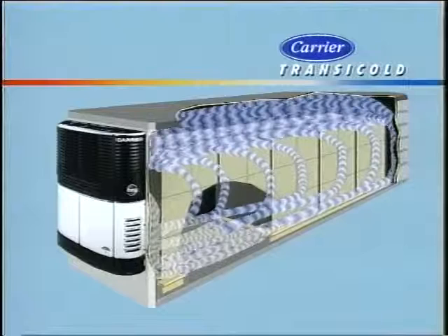To change the set point, simply press and hold either the up or down arrow key. You will notice that when the set point is above 0 degrees, there will be a plus sign in front of it. If that point goes below 0 degrees, a minus sign will appear. The message center will show directions: up, down to scroll, then equal to save. Continue to hold the arrow key until the temperature you want is shown in the display.